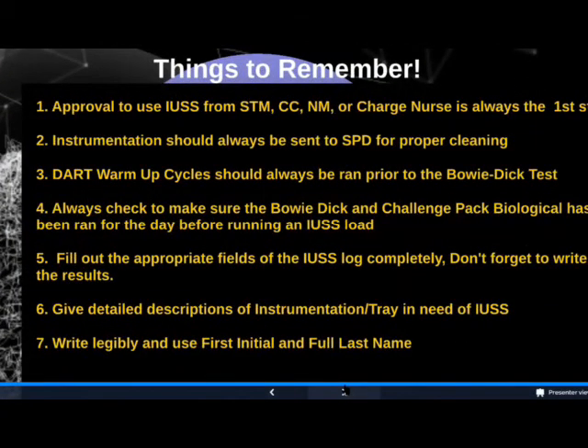So a summary, things to remember: approval to use the IUSS from the STM, clinical coordinator, nurse manager, or charge nurse is always the first step. Instrumentation should always be sent to SPD for proper cleaning. The DART warm-up test should always be run before performing a Bowie-Dick test. Always check to make sure the Bowie-Dick and the challenge pack has been completed for the day and that it has actually passed. Fill out the appropriate fields of the IUSS log completely. Don't forget to write the results and give detailed descriptions of instrumentation, in case, of course, we need to order more of that tray.